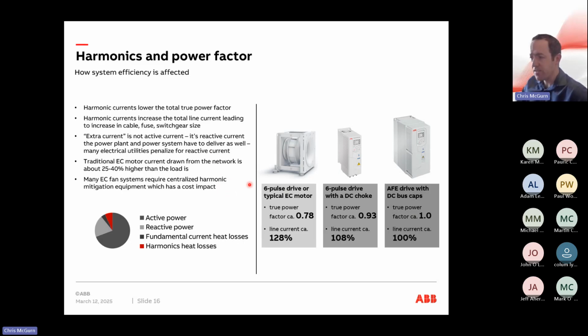So you'll see here a little diagram of how the harmonics and power factor are affected whenever you're using a standard drive, which is a non-ultra low harmonic drive. Because of the harmonics that are impacted by running this, the true power factor it's actually seeing is 0.78, and the line current is 128%. So let's say you're running 100 kilowatts, you're actually drawing 128 because of the impact of harmonics on your system.